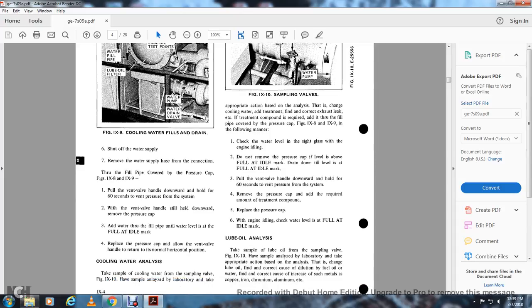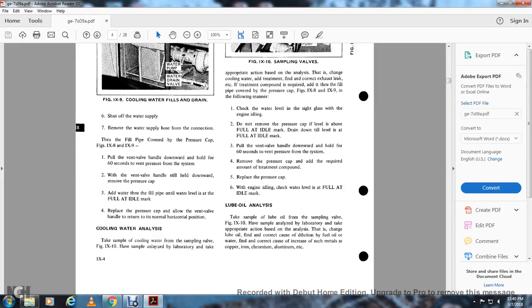Lube oil analysis: Take a sample of the lube oil from the sample valve (figure 9-10) and have it analyzed by a laboratory. Take appropriate action based on the analysis. If changing the lube oil, determine the cause — dilution by fuel oil, presence of water, or an incorrect increase in metals such as copper, iron, chromium, aluminum, etc.